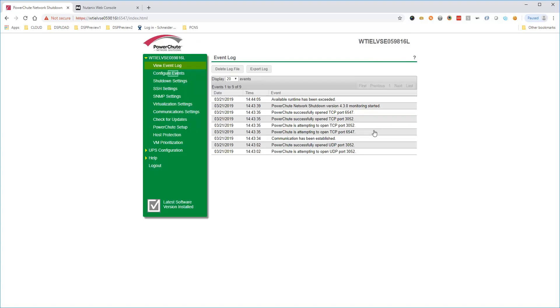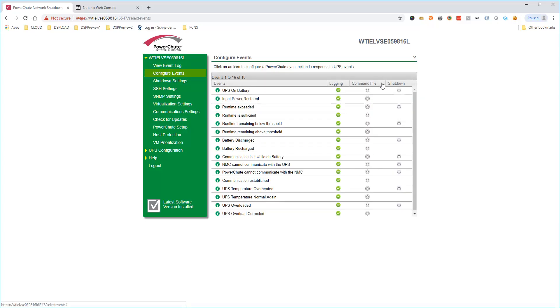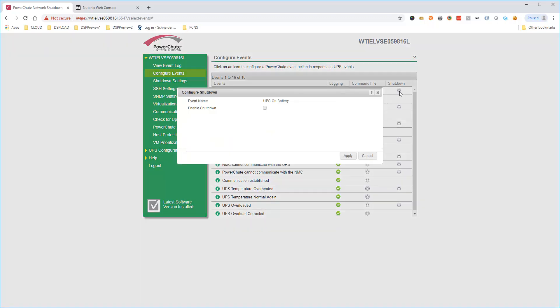PowerChute shuts down by default when a low battery condition occurs. To configure shutdown actions for other conditions, select Configure Events. To enable shutdown when a power outage occurs, choose UPS on battery and click the gear icon. Select the checkbox to enable the shutdown action and set the required delay — this is the amount of time the UPS is on battery power before PowerChute will start the shutdown sequence. Click Apply to save your changes.